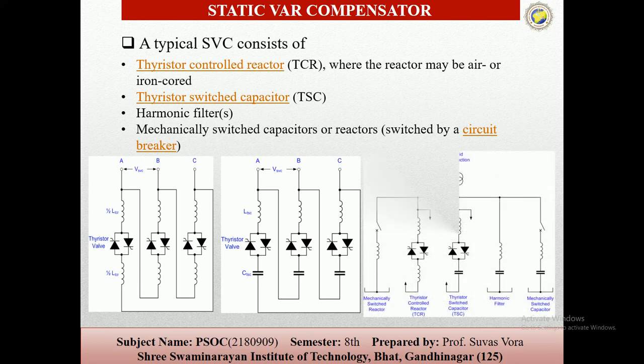So these are the different types of constructions. This one is the mechanically switched reactor, this one is the TCR system, the TSC system, and the harmonic filters, where an LC filter will be used, and mechanically switched capacitors. So these are the different types of constructions of the SVC systems.